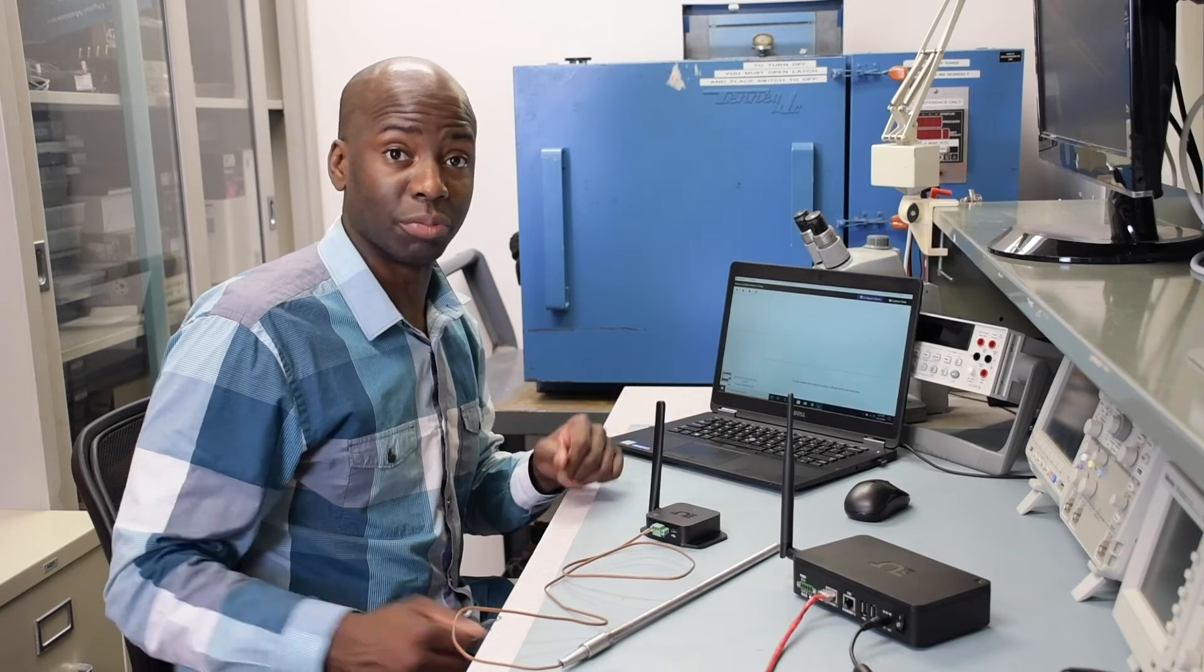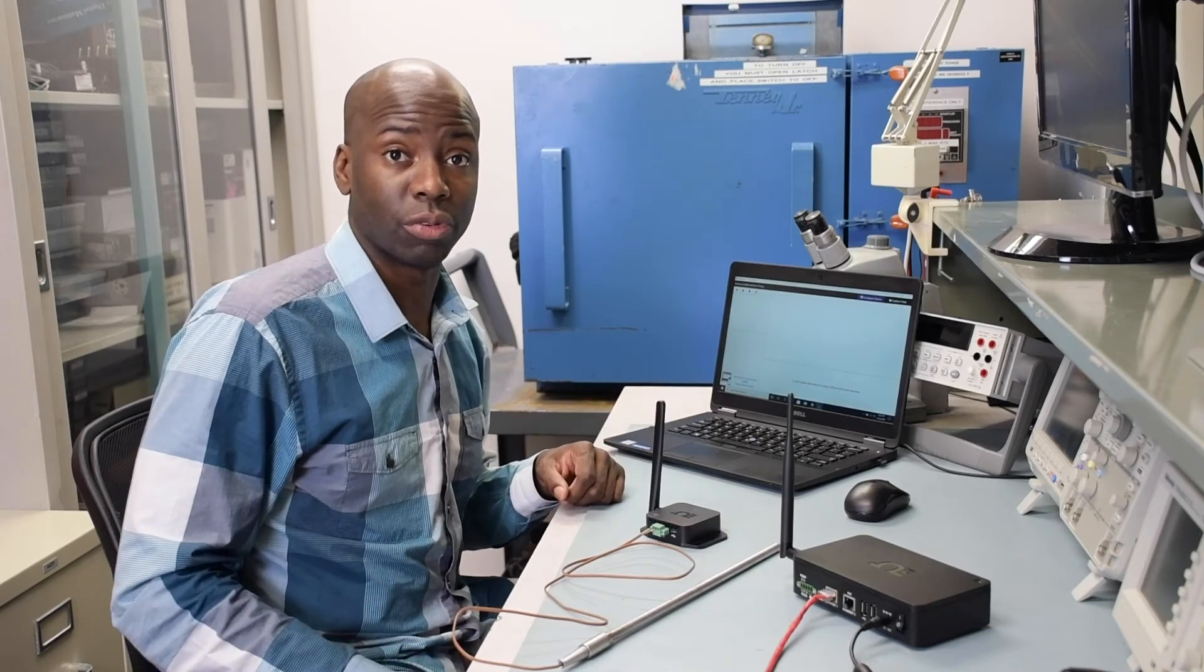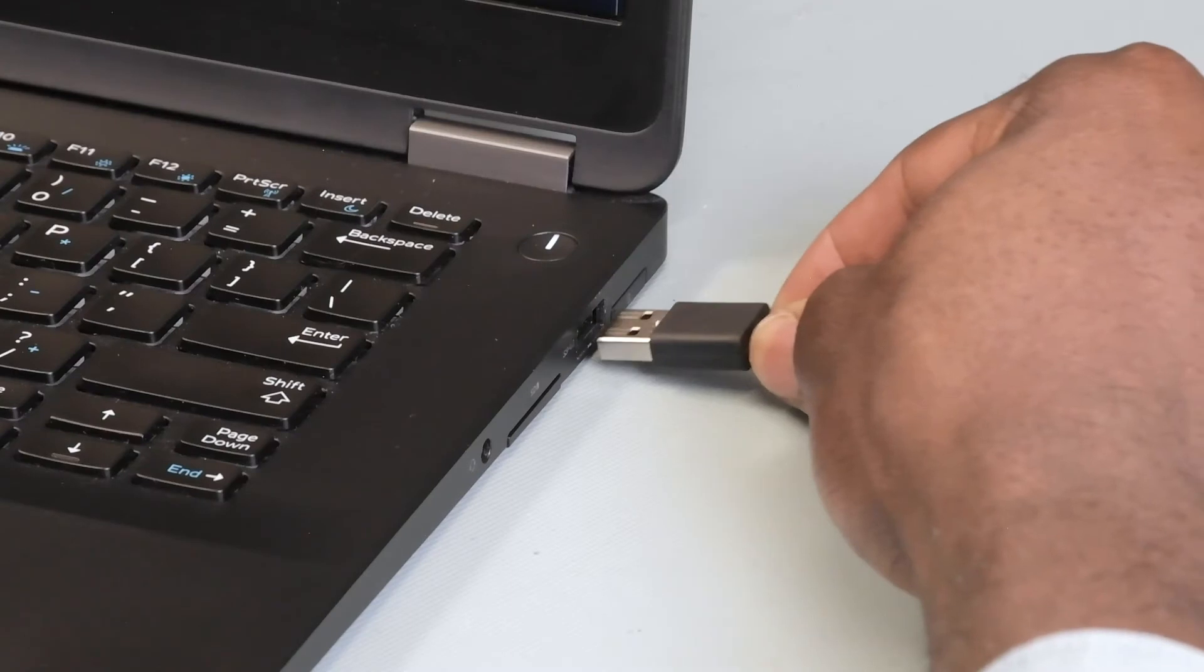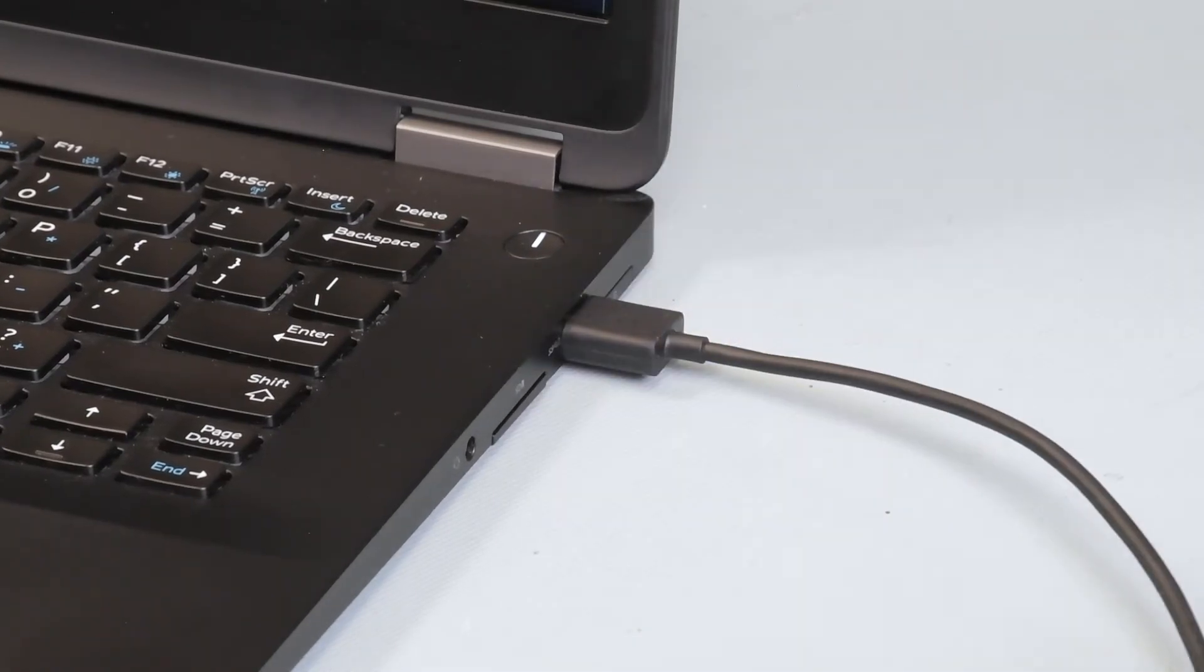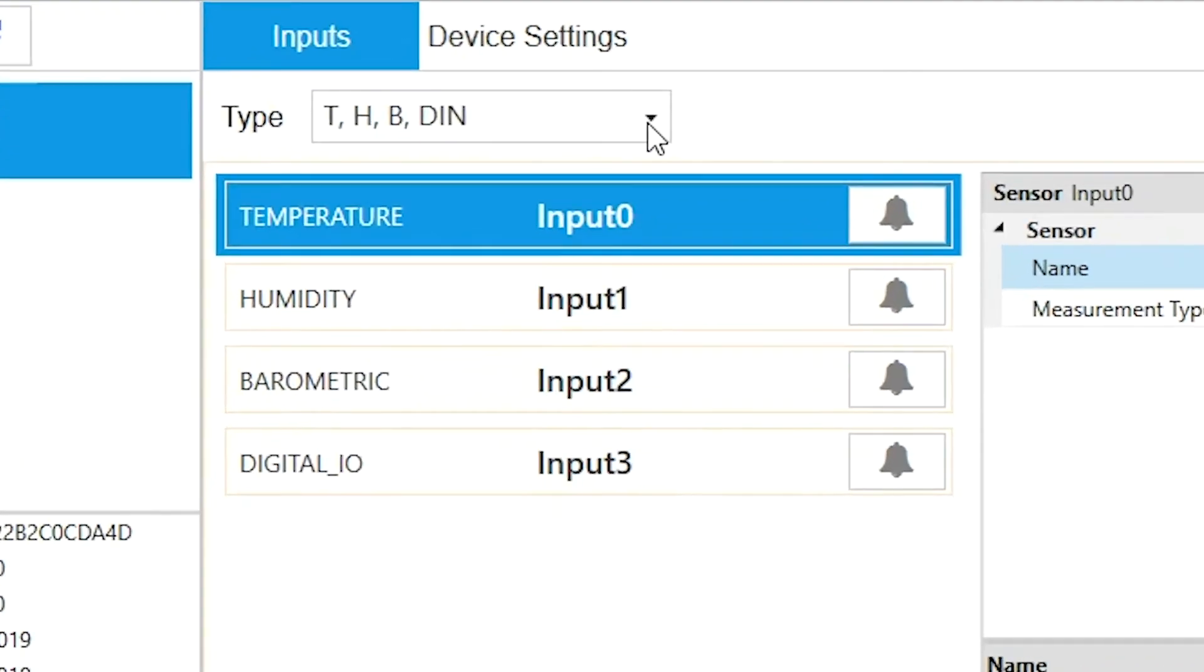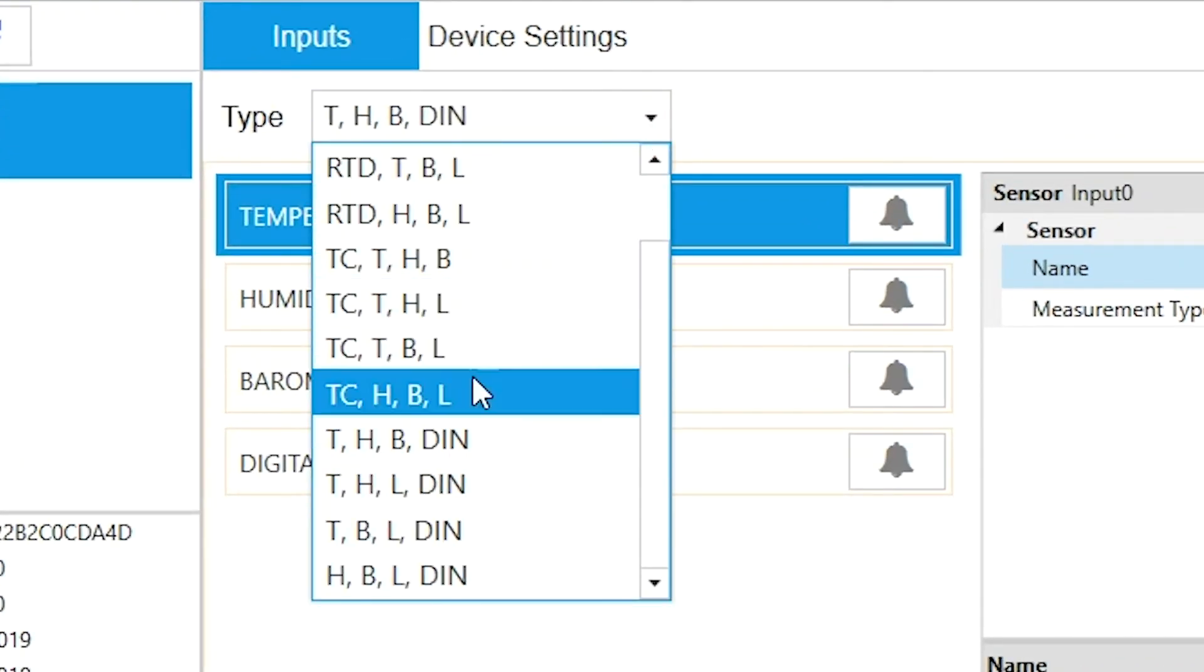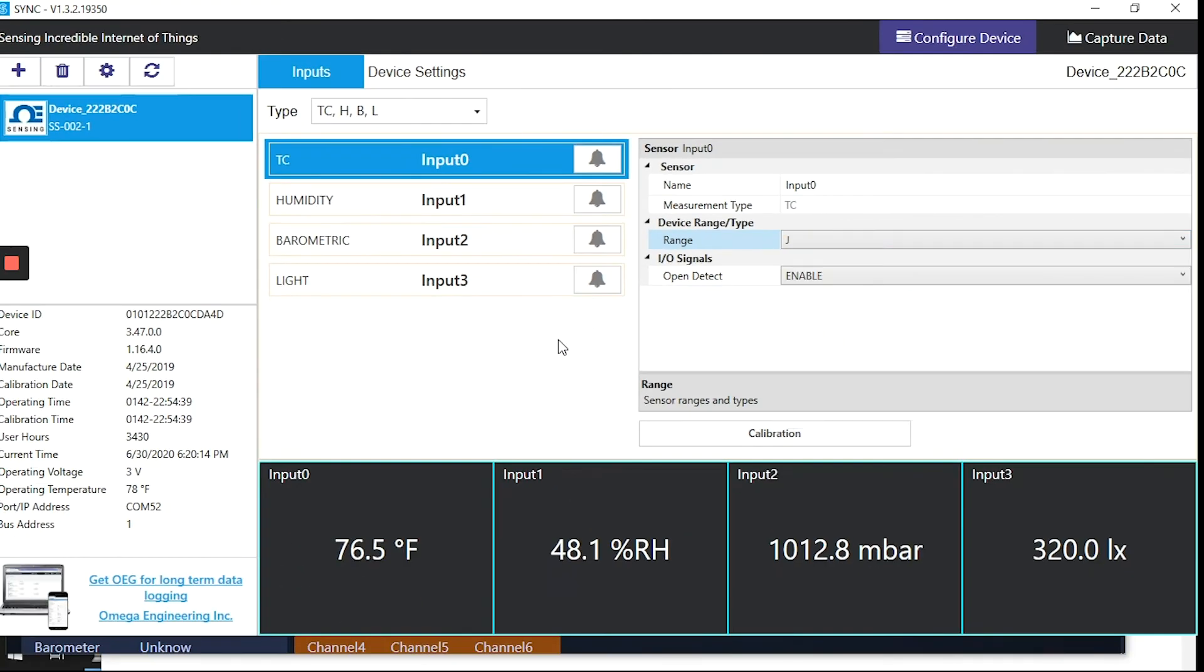Now we'll configure the sensor mix using the Sync configuration software. Connect a micro-USB cable from the smart sensor to your PC running the Sync configuration software. Once your device has been auto-detected by Sync, go to the inputs interface and click the type dropdown, where you'll choose which sensor your device is equipped with. And if it has an SS002-1 like this one, you can choose a mix of any three out of the four internal sensors, plus the external sensor we just hooked up.